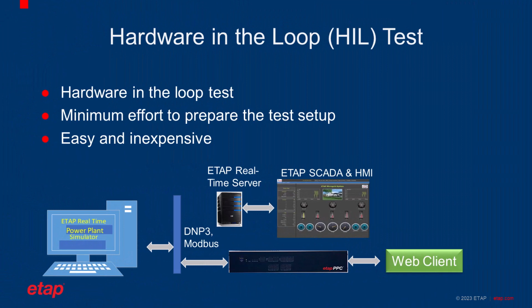Okay, now let's get to the final part of this session, which is the hardware in the loop test. So far, we saw the result in ETAP environment. However, ETAP can be used as a real-time simulator and simulate the behavior of power plant. With this capability, we can deploy the logic inside the actual EPPC hardware and establish a communication between the hardware and ETAP software. This gives us the flexibility to test our logic and our hardware in HIL tests, which makes the process of testing and debugging very easy and inexpensive.